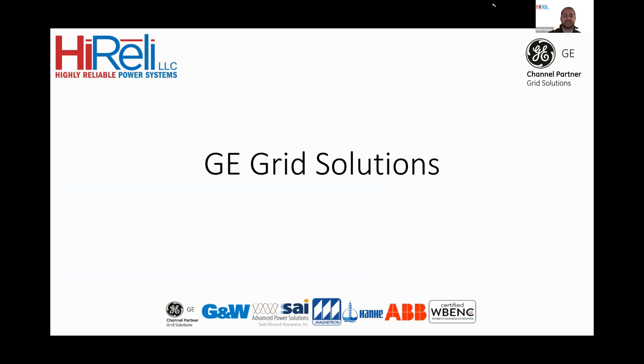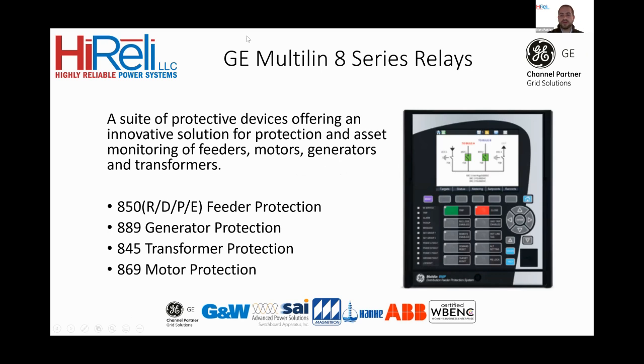Starting with the protection and control side, the Multilin 8 Series relay. The 850R for reclosers. This is a universal recloser, switch, and sectionalizer controller. You have the 850E for industrial feeder protection. You have the 850D for distribution feeder protection, which can handle 2 distribution feeders at once. And you have the 850P for pad mount feeder protection. So this will handle multiple feeders for your pad mounted switches. You also have the 845 for transformers, 889 for generators, and the 869 for motors.